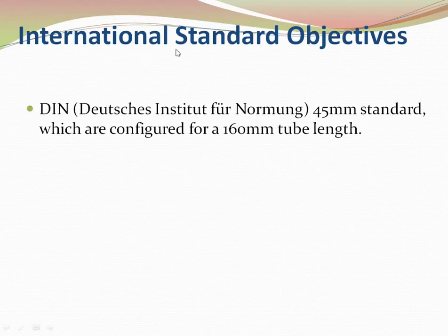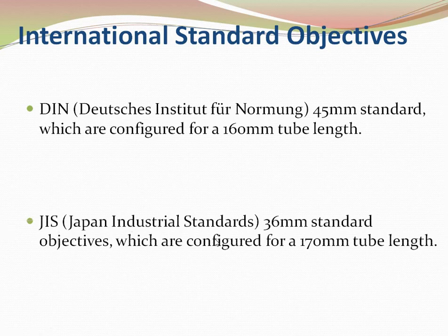There are two standards for objectives. DIN is the 45 mm standard configured for 160 mm tube length. The other is JIS — Japanese Industrial Standard — which is a 36 mm standard objective configured for 170 mm tube length.